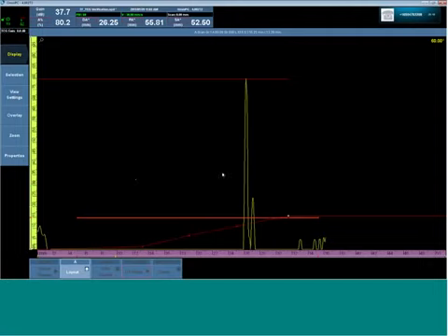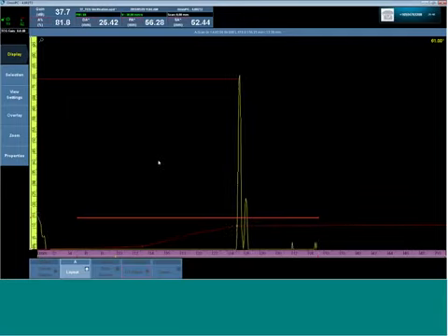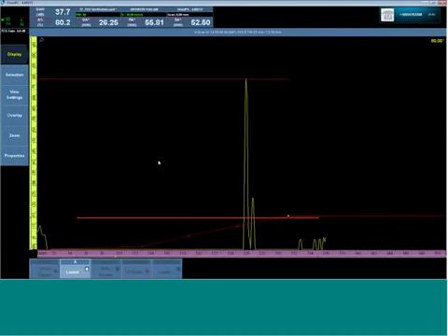It's linear, it's repeatable, the time base can be calibrated, the amplitude and TCG can be calibrated. So in regards to this being a new technology, that's true, but in fact, we're using all the old rules of physics. So our ability to comply with conventional procedures and existing qualifications is often fairly easily repeatable.